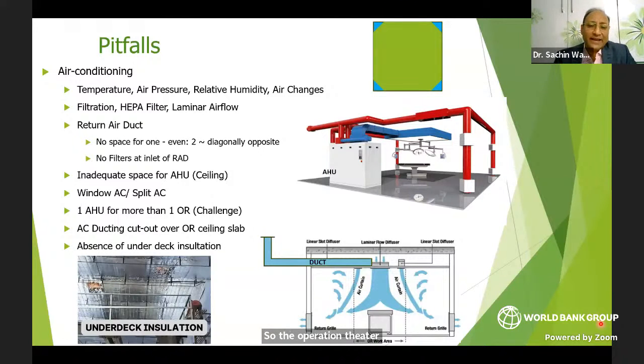So the operation theater requires dedicated AHUs, air handling units, which have triple stage filtration. Not only the support areas - we have to find an appropriate location for the AHUs also. The blue thing you see is the supply of purified air into the OT, and here you have your terminal HEPA filters, which is a 0.3 micron filter, from where the air is thrown onto the table.